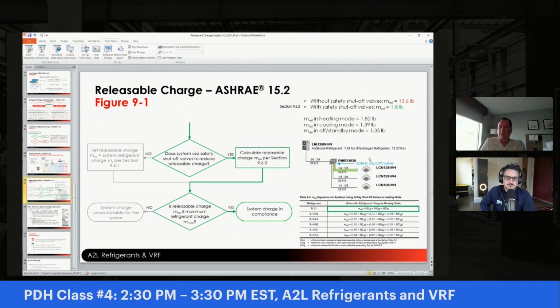As I mentioned, for these MREL values, the largest number is used in the calculations. This table shows the equations used for R32. It's good to note that it's a little tighter and more complicated for 454B, so your MREL for 454B will always be larger than R32 for the same size system.